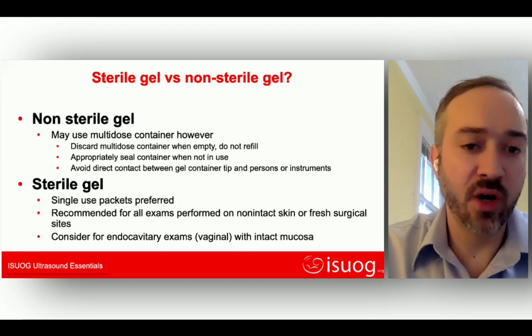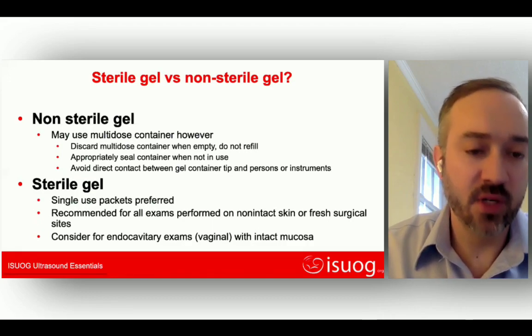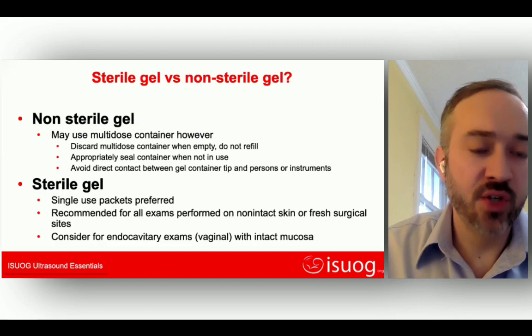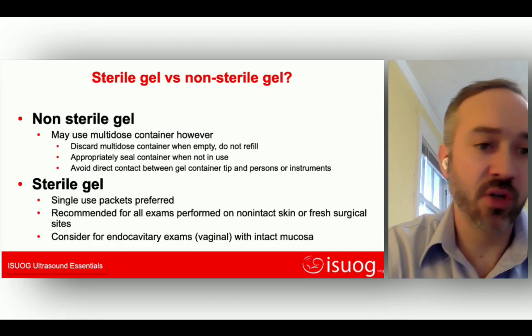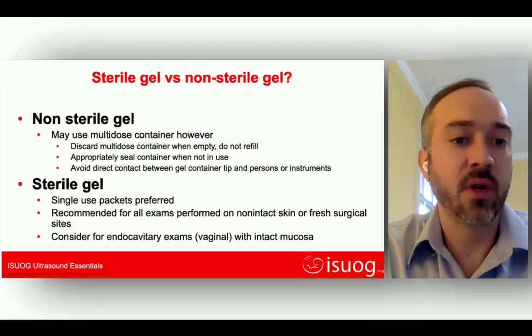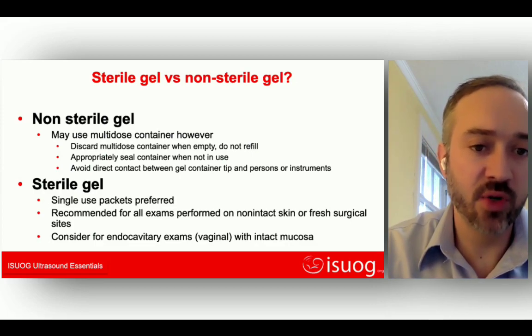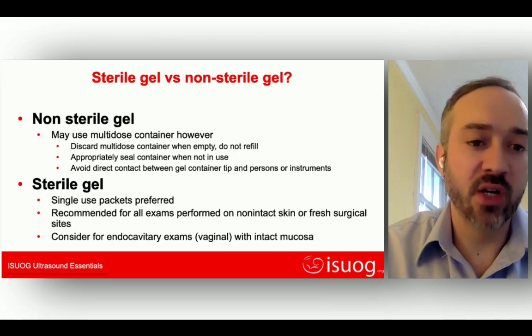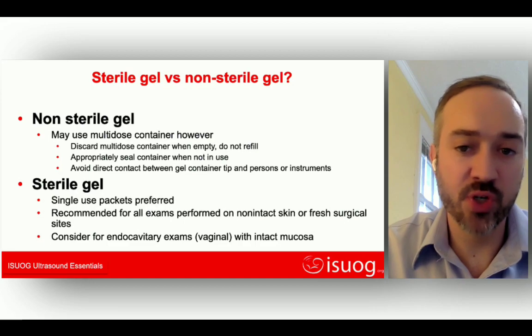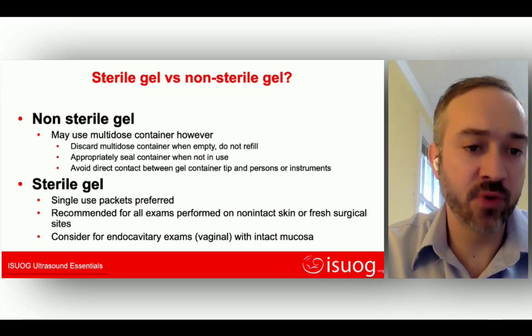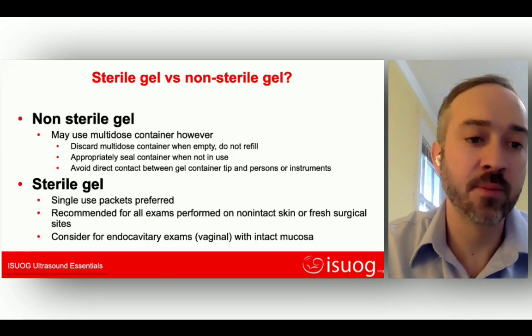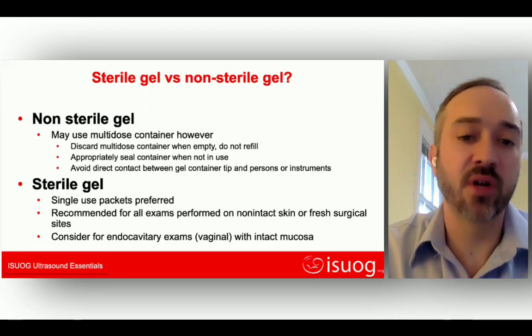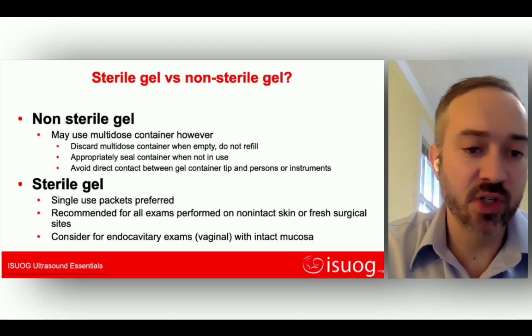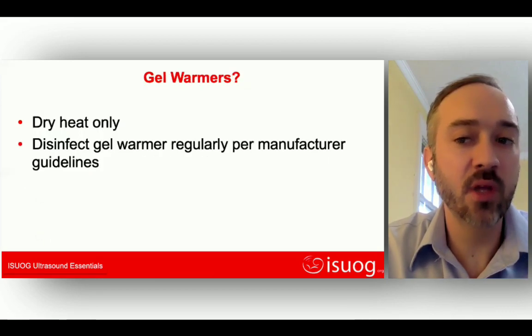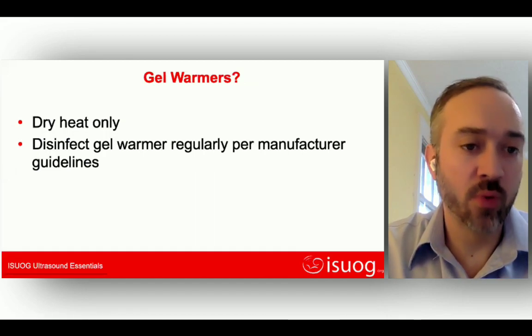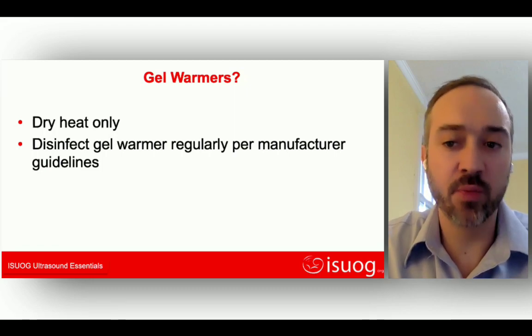So some thoughts on non-probe related maintenance and non-probe related things to keep safe with the machine. As you know, there's sterile and non-sterile gel. When you use non-sterile gel, I'd recommend using multi-dose containers. However, if you can, discard the multi-use containers when empty, don't refill them. Seal the container when it's not in use, and don't directly contact the container between the tip and the person or instruments. And when you use sterile gel, it's preferred to use a single-use package that you discard after that patient. And this is recommended for all exams on non-intact skin or surgical sites. You might consider these for endocavitary exams as well. If you have gel warmers, use dry heat warmers only, and disinfect the warmers regularly. Don't forget about your accessory equipment.